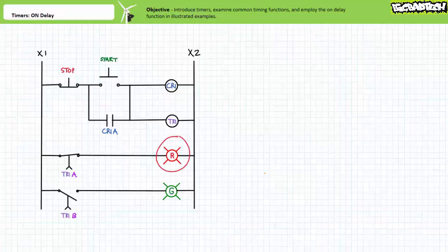Again, note the timer relay delayed the transition of the associated contacts, and thus the response of the pilot lights, for a period of 5 seconds after the start button was pressed. Note, if an operator were to press and release start, and then immediately press and release stop prior to the delay period elapsing, the timer would clear and reset.